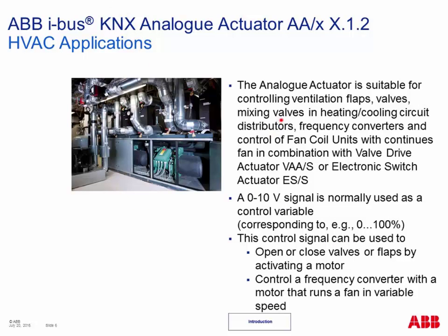So let's go to some more details of this application. Ventilation flaps are a typical application where you have to open and close the airflow in a tube, for example, like here. Or you have to control valves, for example mixing valves in heating and cooling circuits, where you have to mix the incoming temperature flow with the return flow to get the right outgoing temperature for the water for the system.